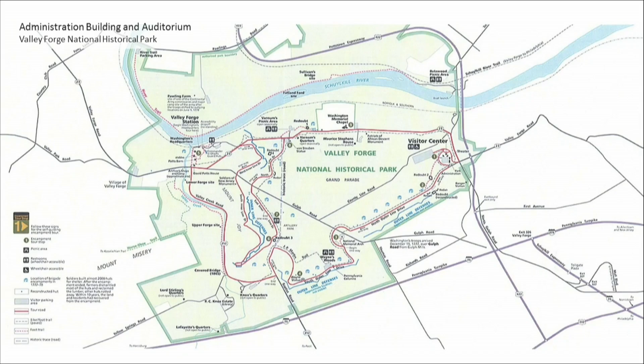The purpose of the current task order is to modernize the existing HVAC systems in both the administrative building and the auditorium, by developing design solutions for the replacement of the existing 100-ton water-cooled reciprocating chiller, for the replacement of the electric resistance variable air volume boxes and supplemental electric baseboard heat that provides heat to both buildings, and for new ductwork to distribute the conditioned air more effectively.